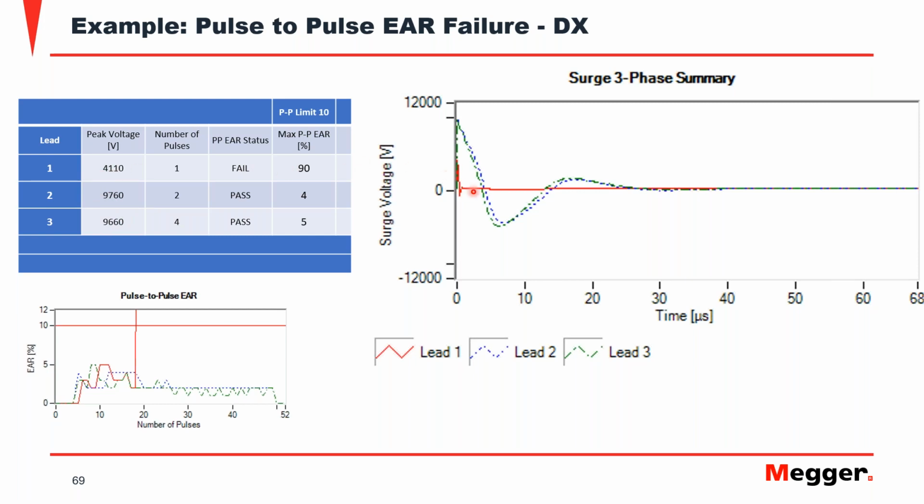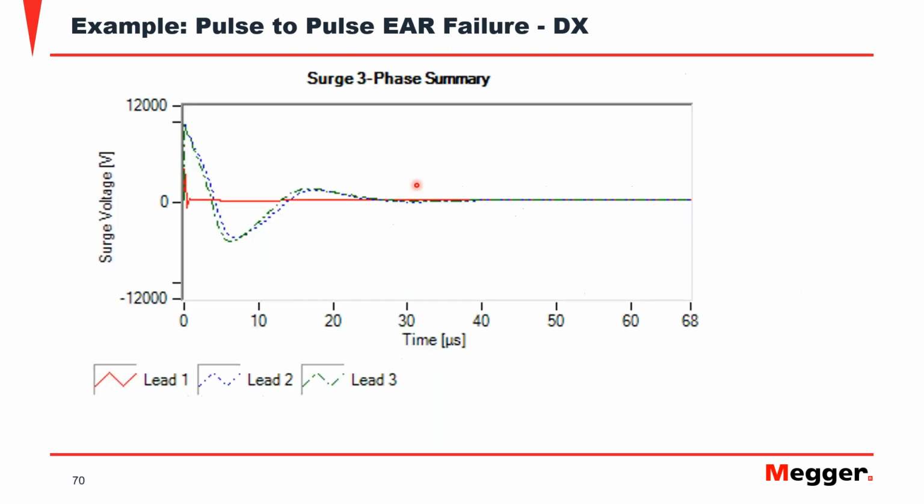You can see here the difference. These two were very similar. Now, they were not perfectly aligned because the rotor was in the machine. Actually, everything was in the machine. The machine was in the factory. But the last one actually failed way below the other two. There was a lot of argument that day. Hey, is the problem with the leads? We changed the leads, we swapped, but the problem was always on the same lead. This is just a blowout of the same failure.